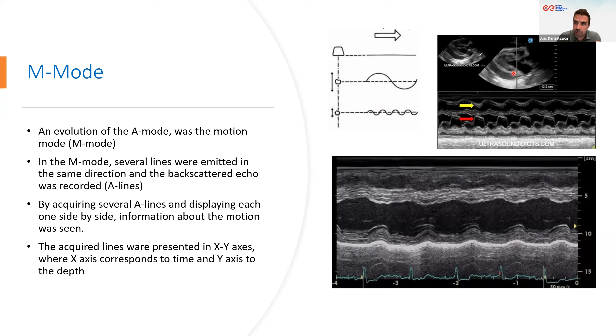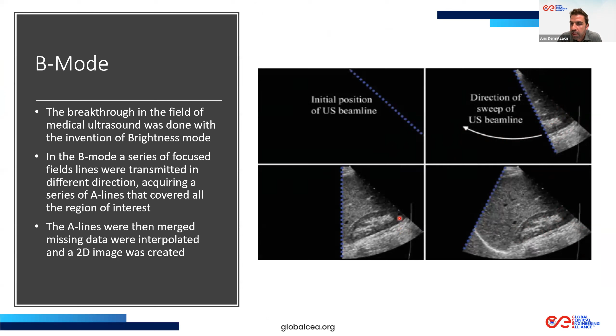Then we have the B mode, what we all know as ultrasound image. It was a breakthrough in ultrasound imaging. B comes from brightness. And what we do here, exactly as the radar, we scan an area. So we are sending A lines and we are steering them in a whole area. We scan them and we print one next to the other, resulting in our final image. We have many different arrays to do that. The most important categories are linear and convex array probes, in which we have the elements, piezoelectric crystals, one next to the other. And what we do is that we scan by exciting the next element of the aperture and resting the last one. And we do this sequentially in order to scan the whole region underneath.